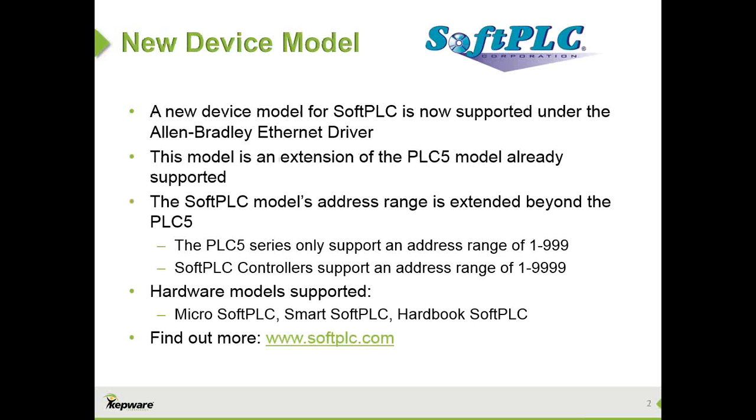Another improvement was to our Allen Bradley Ethernet driver. There's a new model called the Soft PLC, which is an extension of the earlier PLC5 model. It extends the address range for the PLC5 model previously supported in this driver. PLC5 supported 1 to 999 as an address range, and we add an extra digit, going up to 9999 for the Soft PLC.